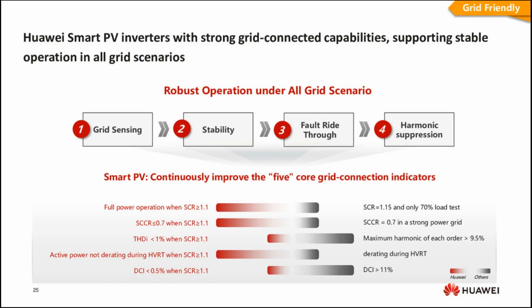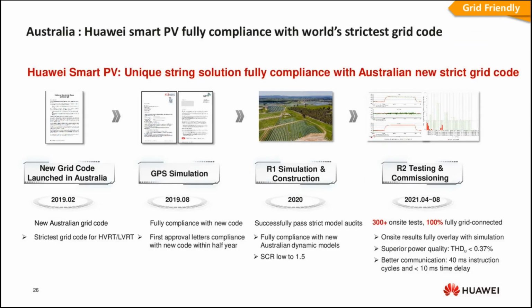We see locations and installations where the short circuit ratio might go below 2, even around 1.2 or 1.1. Integrating grid sensing features, stability algorithms, passivity, and full compliance in fault ride through for low and high voltage, plus power system quality through harmonic suppression and damping, gives this product complete intelligence for utility scale installations.